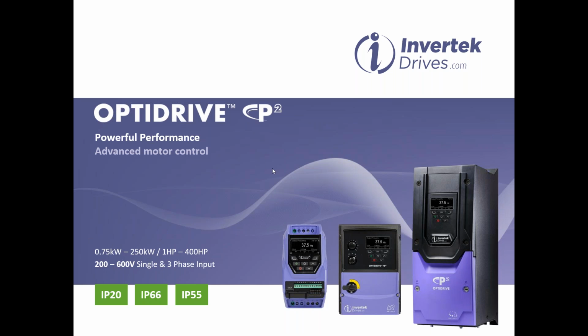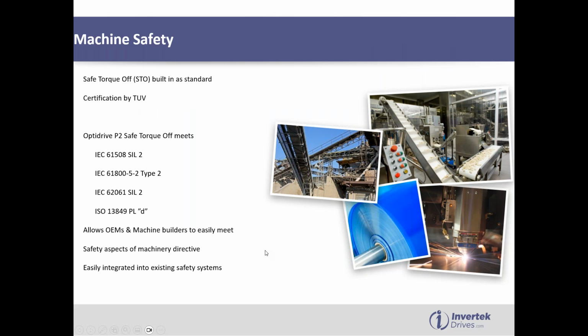So the P2, we have the same power range as the Eco, so 0.75 to 250 kilowatt, and in IP20, IP66, and IP55 units. The P2 has a focus on industrial performance type applications. So we have safe torque off built in standard. That's safe torque off to SIL2 performance level D. And it just makes it nice and easy for OEMs and machine builders to integrate it into existing safety systems.